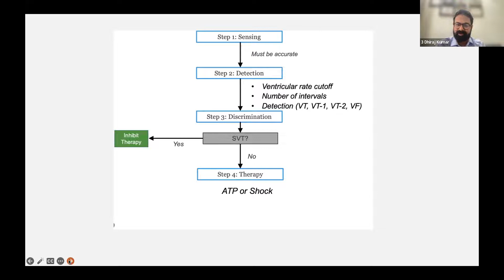Now, what is important is sensing. As I told you, sensing is very important for the devices. When a device senses a signal, it looks at the signal's amplitude and it looks at the signal's frequency. Why is it important to look at the two together? Sometimes these frequencies of more than 100 are supraphysiological. Intracardiac events don't have frequencies more than 100 hertz. If a device senses something beyond this range, it immediately knows that it is something related to noise, electromagnetic interference, or a myopotential, basically some kind of tremor or muscle potential. And therefore, it does not deliver therapy. It immediately knows that it is a non-physiological signal.